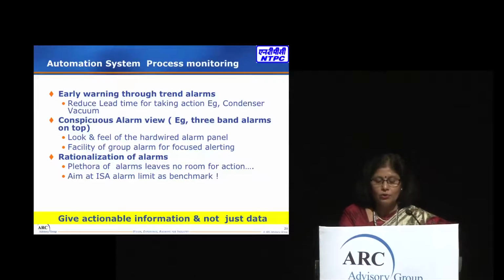So for that, you have to capture an early warning system. For example, a slow changing parameter like condenser vacuum. If you can capture that and give some early alert to the operator, the operator can take timely action and really add value to the system.